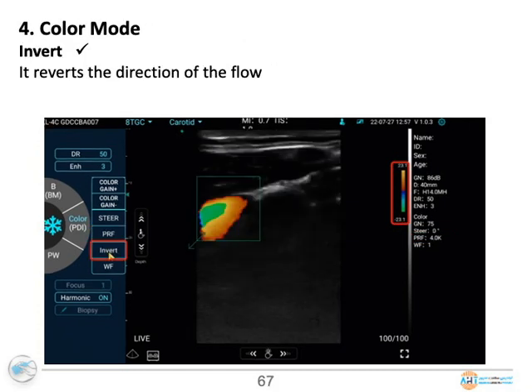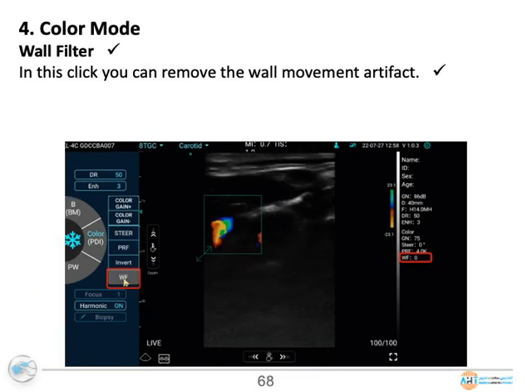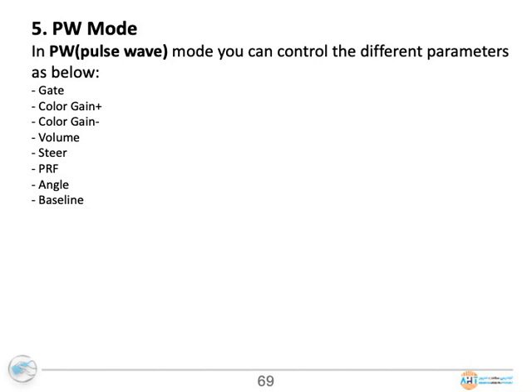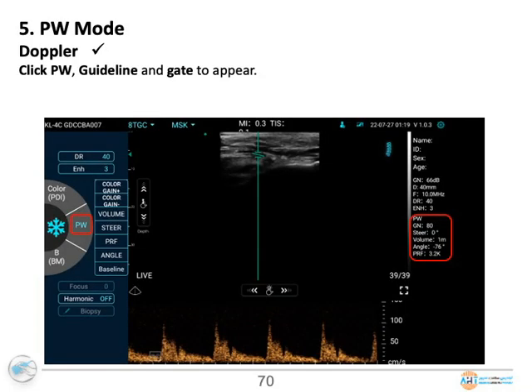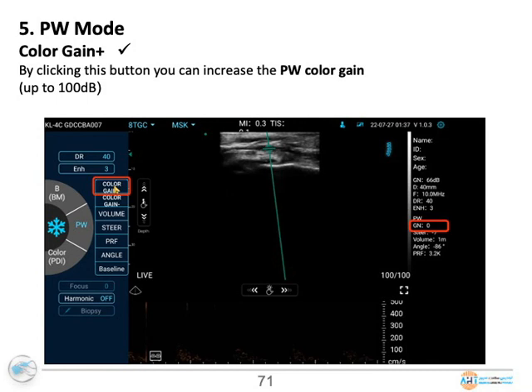Color mode, invert. It reverts the direction of the flow. Color mode, wall filter. With this click, you can remove the wall movement artifact. PW mode. In PW, pulse wave mode, you can control the different parameters as below. PW mode. Doppler. Click PW guideline and gate to appear. PW mode. Color gain. By clicking this button, you can increase the PW color gain up to 100 dB.